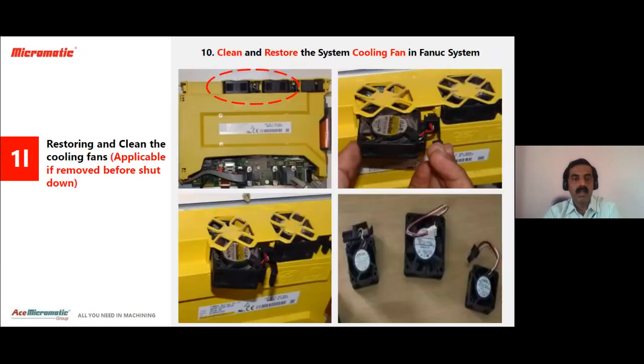Now the next point is, so many days the machines are in a shutdown, so we need to clean the cooling fan. This is also applicable to all machines in FANUC as well as some Siemens machines, if the fans are available. So what we have to do is clean and restore the system cooling fan in the FANUC system as shown in the picture with a red circle. The procedure is already given and even shown in the photos. So we have to ensure to clean and restore those fans.